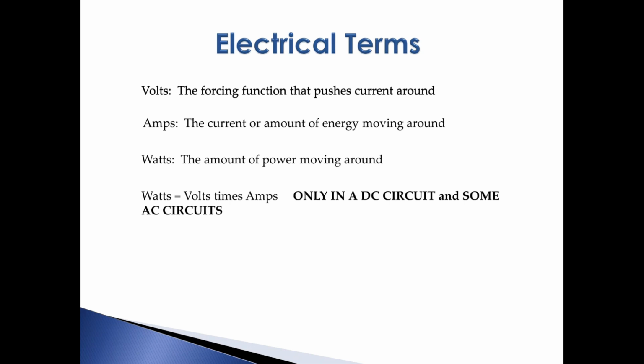That's only going to be true in a DC circuit 100% of the time. It will be true in some AC circuits, but those are more complicated, and sometimes multiplying volts by amps only gives you volt-amps, not watts.